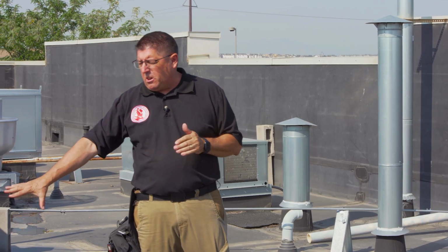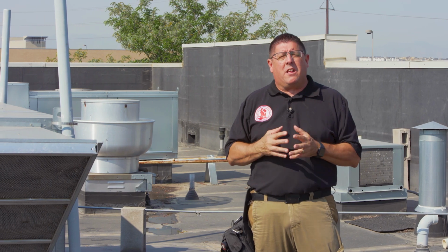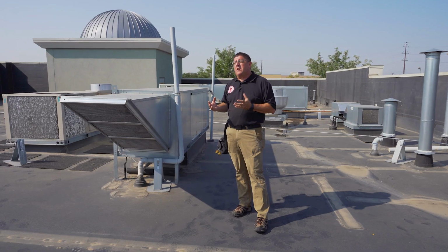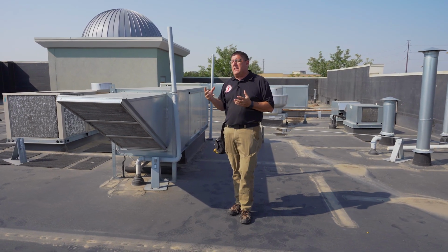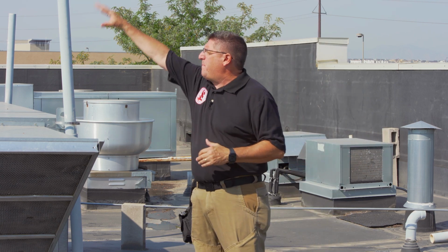So on this particular unit here, I've got this wonderful boot that was installed directly under the air intake. Now our challenge with that is that it will immediately exhaust whatever sewer gases are escaping through that plumbing vent and enter right into the makeup air. In this case, they vented it up and above.